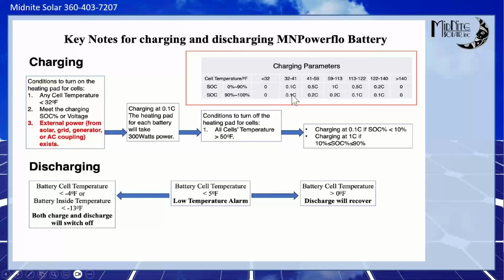So this is another one. Customer will call and say, hey, it's 15 degrees Fahrenheit out, and for some reason my battery is only charging at 1,000 watts instead of 10,000 watts. And that's this temperature derating here. If the heater is on, or if you've got a Powerflo 5 that doesn't have a heater, at 32 degrees or less, we don't charge without the heater. We charge with the heater, of course.